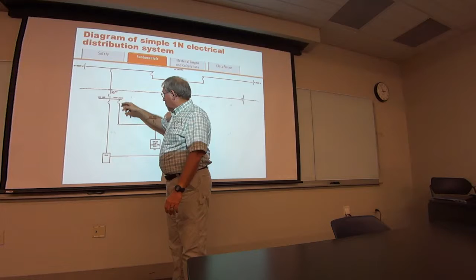5,000 amps is pretty much the biggest thing you can bring power into the building. So if you need more, say a 15 megawatt load, you'll need three of these. Then you come down here, hit a PDU, which steps the voltage from 480 down to 208, then you hit your IT equipment. You might have 480 volts, and this is what we have for the Titan supercomputer.